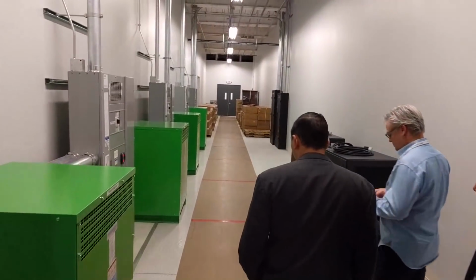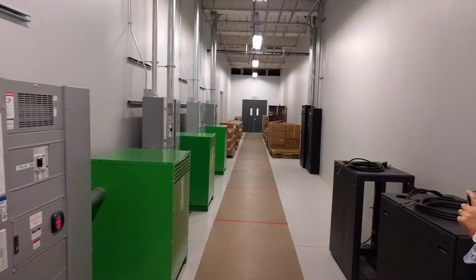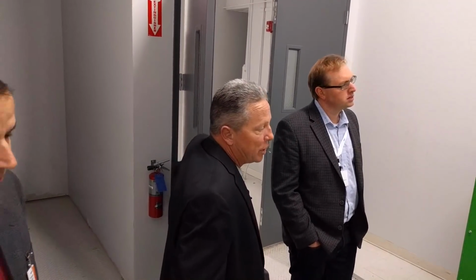So our most recent expansion was the addition of another 1.2 megawatts of transformer power to deliver more power to customers. We're actually expanding our remote power panel capabilities and increasing the number of circuits we can deliver. All those buses you see out on the raised floor are all tied to these. These are special transformers. Most facilities you'll get 208 power, and you can get single phase power and whatever you want. In our case, we had these specially made. They're 240 volt. So we can do 2-pole or 3-phase 240 volt. And what that does is it drives up the efficiency on the power supplies. So even if we get all those power supplies on the raised floor running 2 or 3% more efficient, it's a huge gain when it comes to the electrical bill.